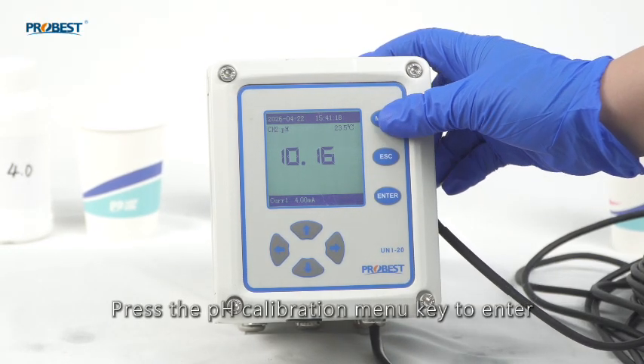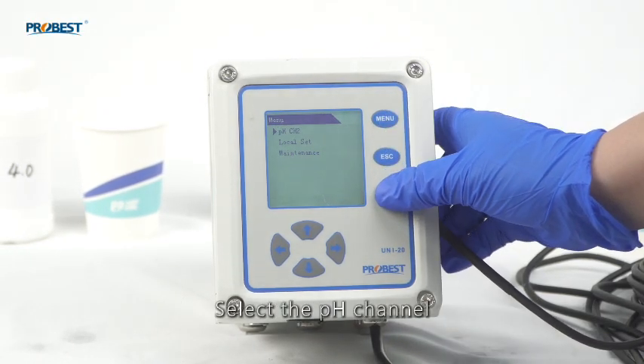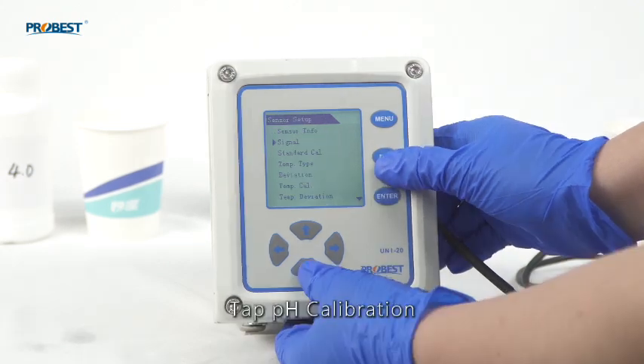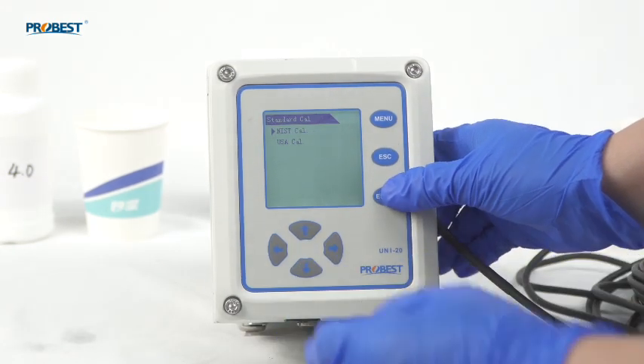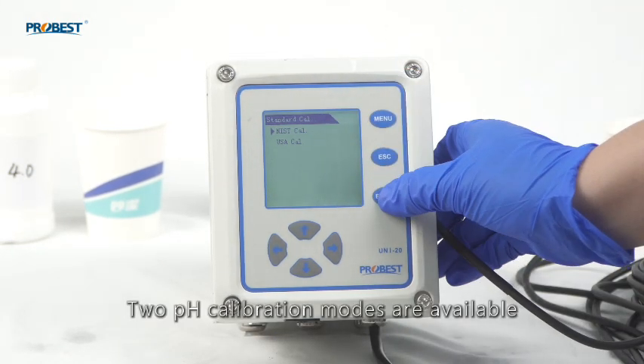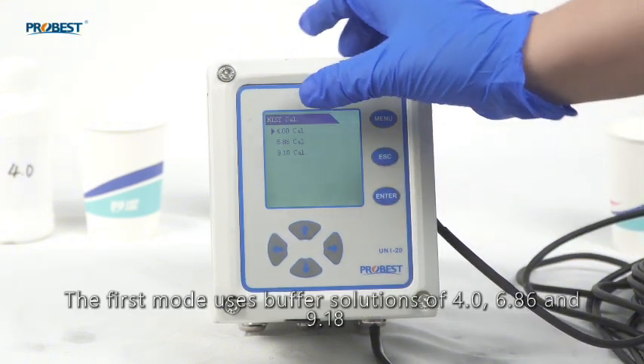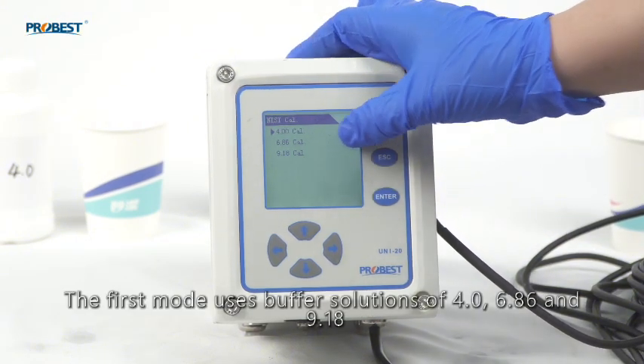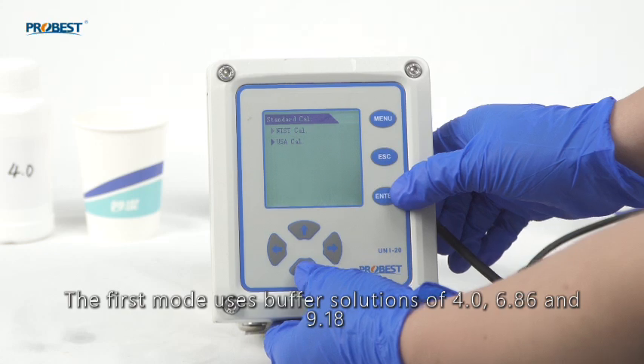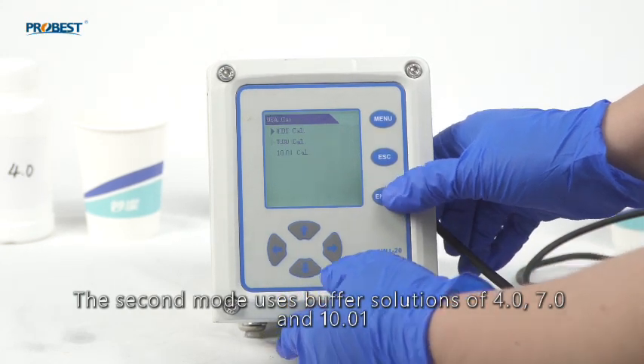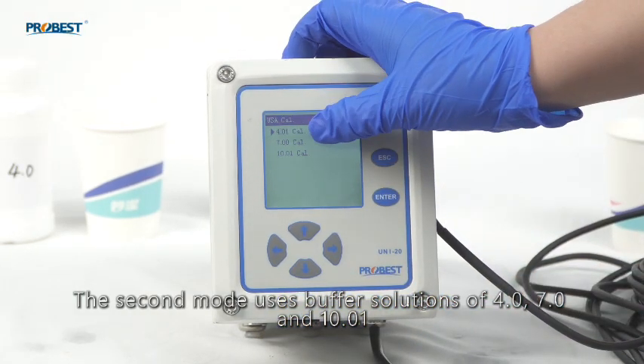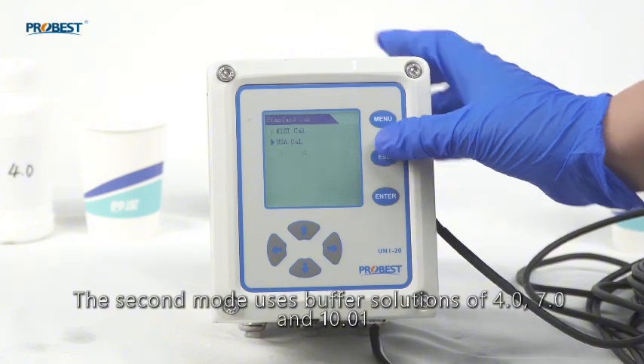Press the pH calibration menu key to enter. Select the pH channel. Tap pH calibration. Two pH calibration modes are available. The first mode uses buffer solutions of 4.0, 6.86, and 9.18. The second mode uses buffer solutions of 4.0, 7.0, and 10.01.